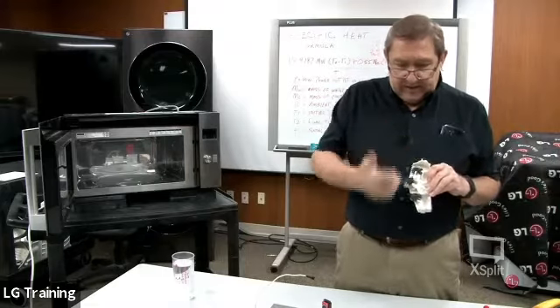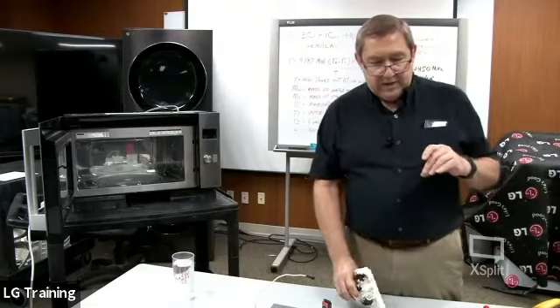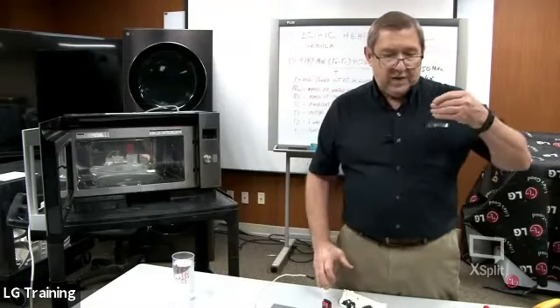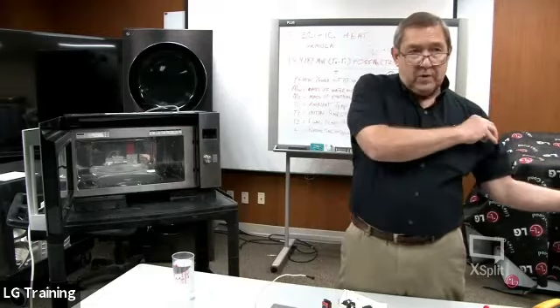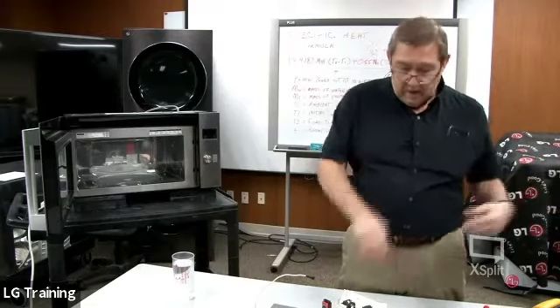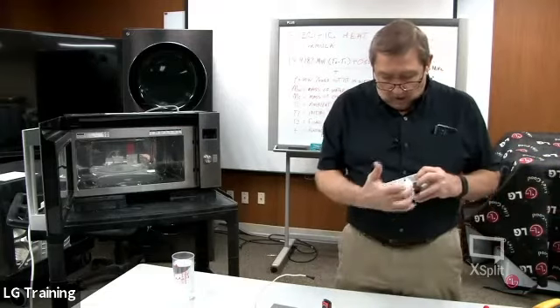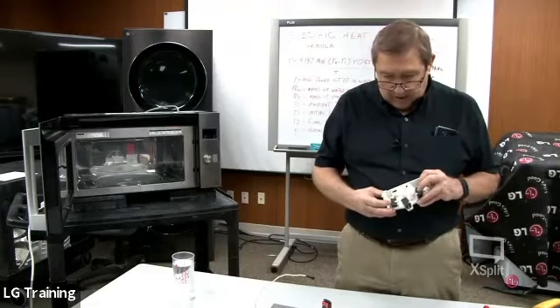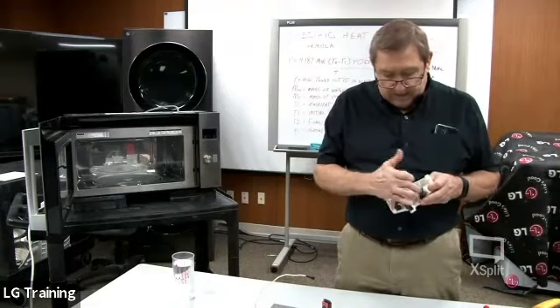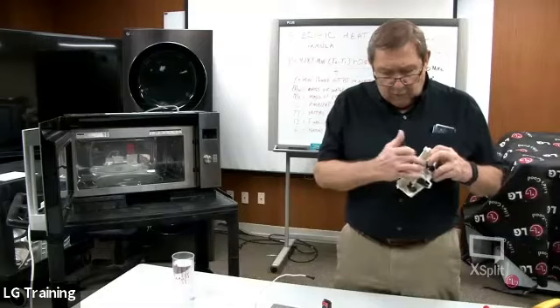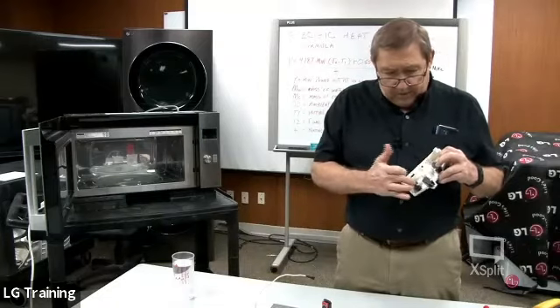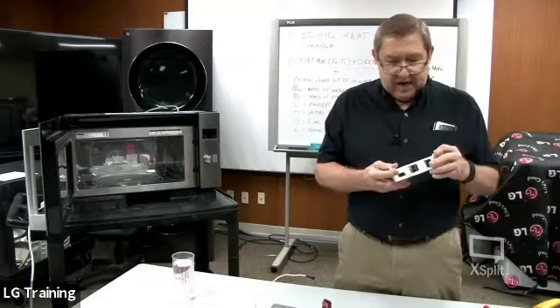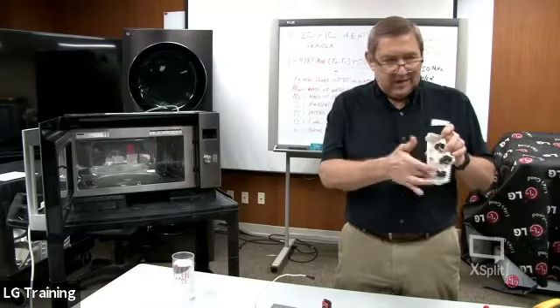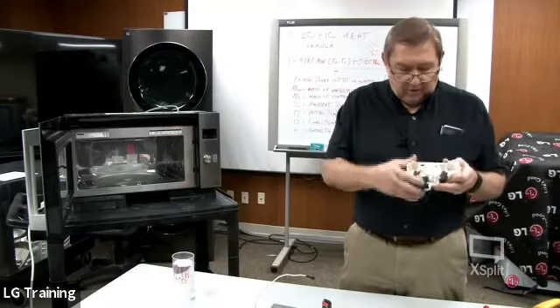It isn't in that live circuit. All it's doing is looking for that switch being open and closed, and it reports right to the main board. So the ones that are really going to probably trip that 20 amp fuse are going to be that primary one or that monitor one. And like I said, you don't have time to guess which one. They're inexpensive, you can just replace all three of them.